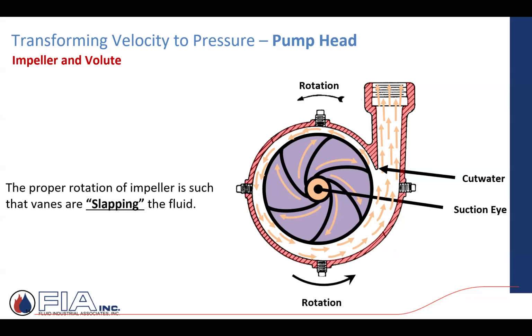And most times, with everything size selected, etc., that's exactly what happens. We'll touch on this a little bit later on, because as you get into larger commercial pumps, and you get into different capacity ranges, you'll start to see efficiencies and why they change. Some of that has to do with the cut water. How much is recirculating? How much is being discharged out?